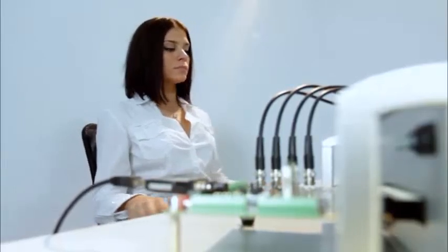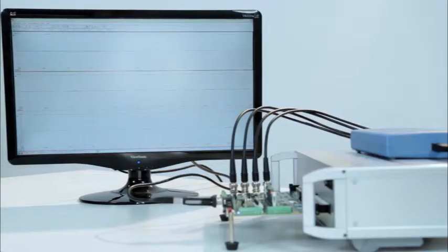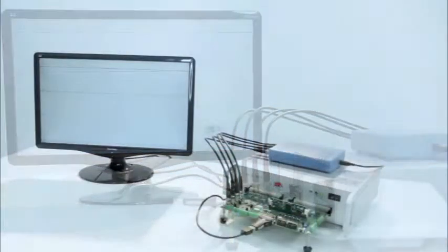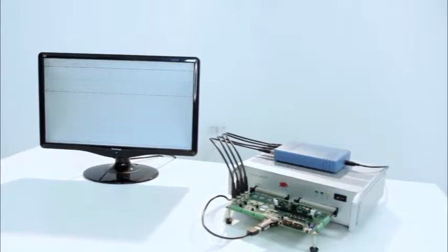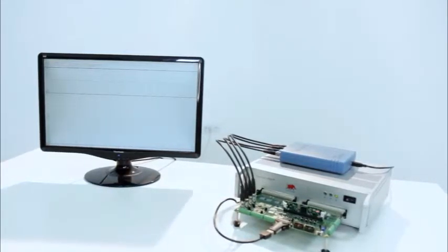Of course, we can continue testing our controller under all imaginable conditions, such as injecting sequences of harmonics, emulating faults, applying different load profiles, etc. Using the Typhoon HIL 600 with the Python API, we're able to automate the process until we are satisfied with the controller's performance under all conceivable conditions, thus greatly increasing quality assurance.